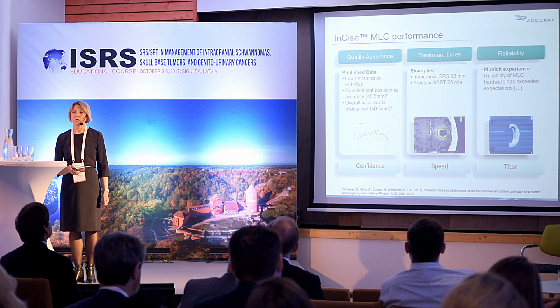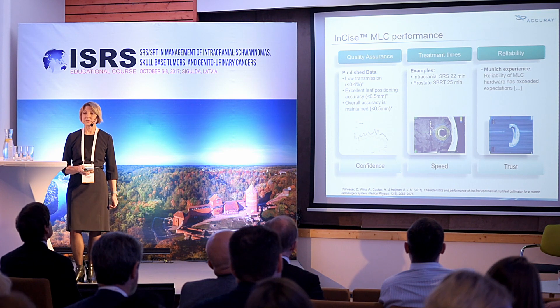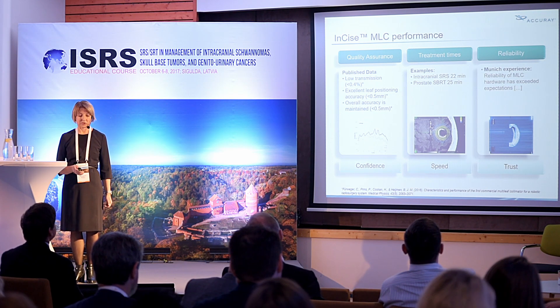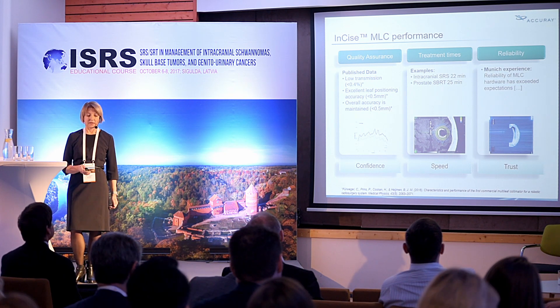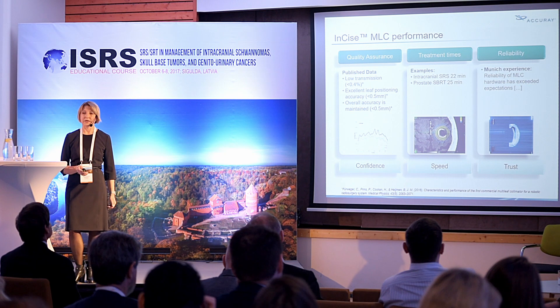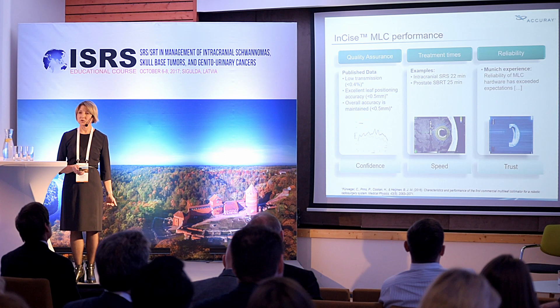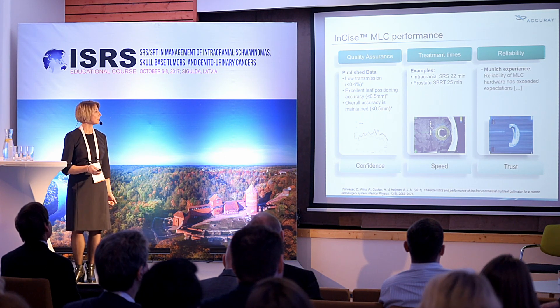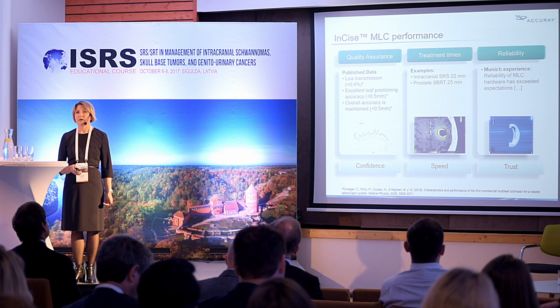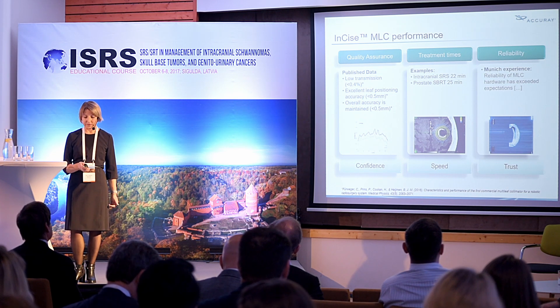CyberKnife is the one system that has an MLC collimator on a robotic construction, called the InCise MLC. The MLC was created to expand clinical indications for treatment and gives the opportunity to treat bigger lesions with a significant reduction in treatment time.